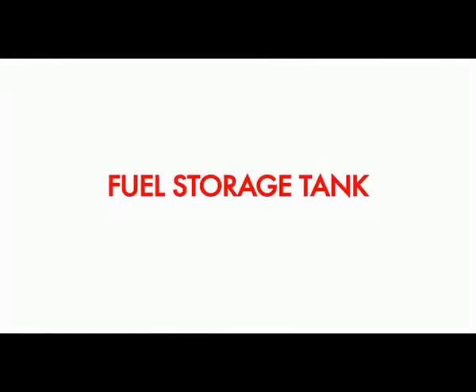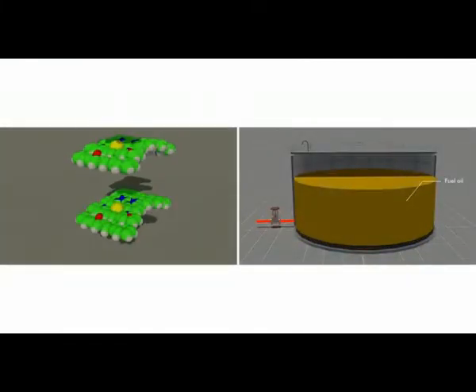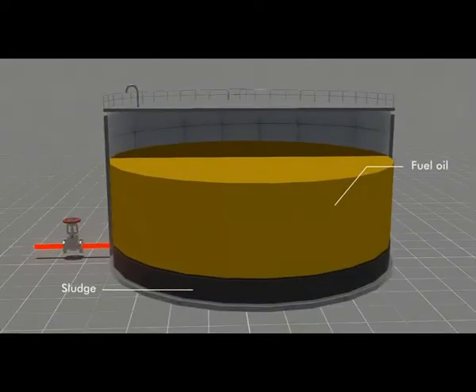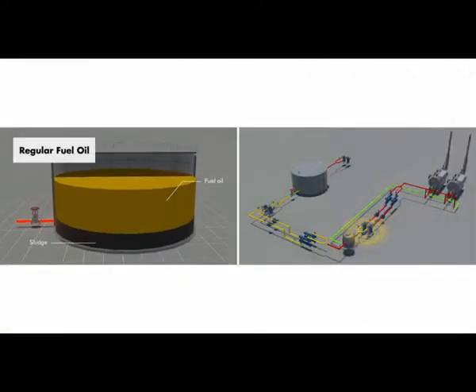Let's take a look at the storage tank. All fuel oils contain heavy molecules called asphaltenes, which tend to build up as deposits. These deposits then settle in the storage tanks as sludge. In time, the sludge makes its way to the pump's suction line and back into the fuel system, causing blockage and disrupting the fuel supply to the boilers.